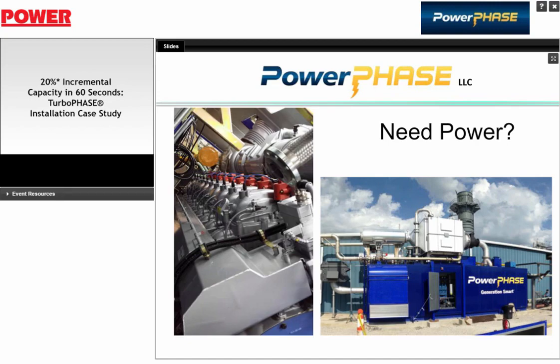the steam cycle. So since our augmentation is really gas turbine centric, it's not like a duct burner that's steam turbine centric. We can add a typical 50 megawatt system on an air-cooled 2-on-1 7FA, where they might start running into problems on their ACC on 100 degree or hotter days. Our system, the incremental power boost at those temperatures, 100 degrees and hotter, might drop from 50 megawatts to 45 megawatts, for example. And your steam turbine is losing power, but you're gaining it a factor of 10 faster on the gas turbine. So it's really a good product to boost the power on really hot days.